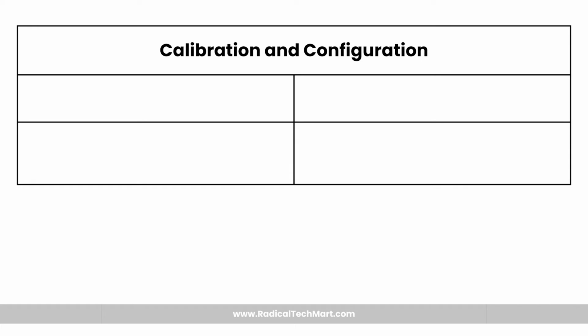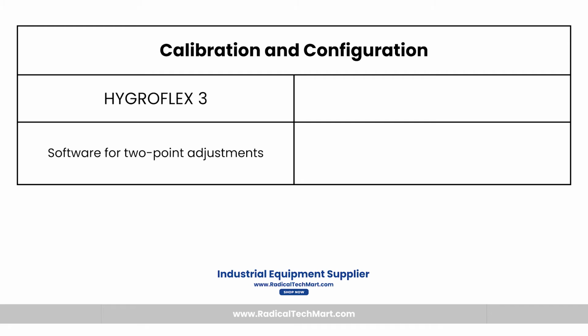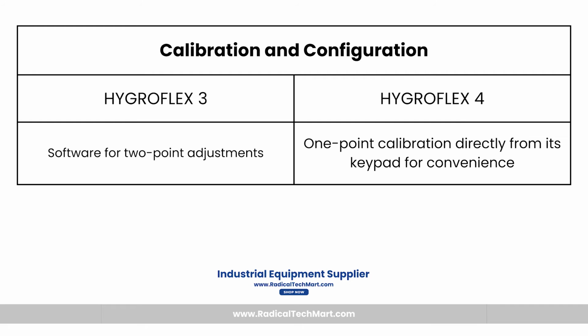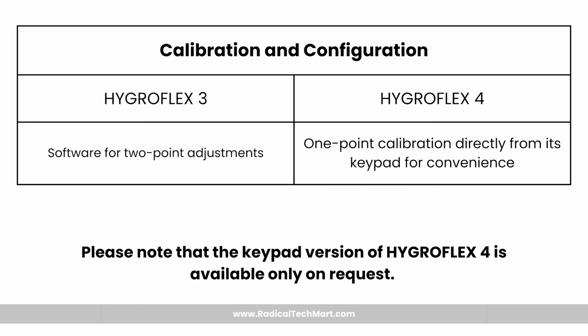Calibration and configuration for both series is as follows. HygroFlex 3 requires software for 2-point adjustments, whereas HygroFlex 4 allows 1-point calibration directly from its keypad for convenience. Please note that the keypad version of HygroFlex 4 is available only on request.